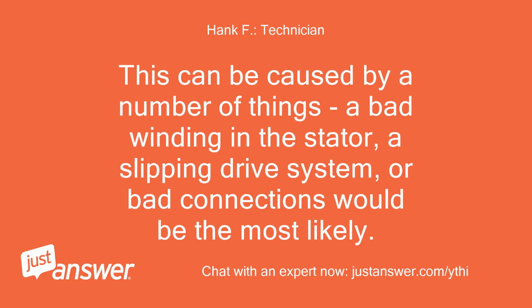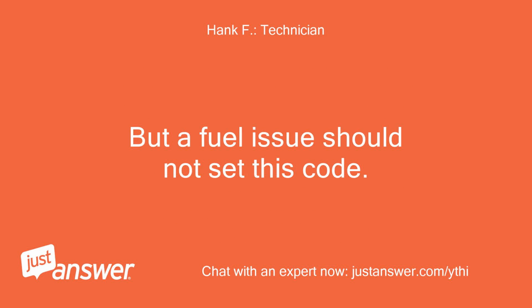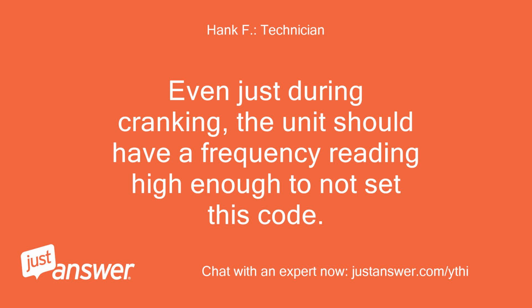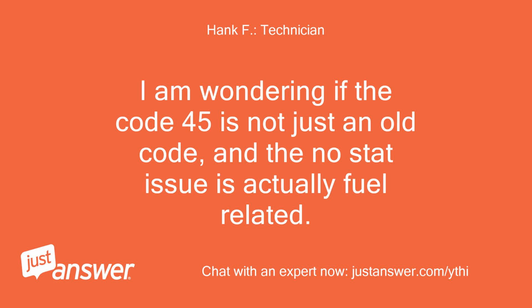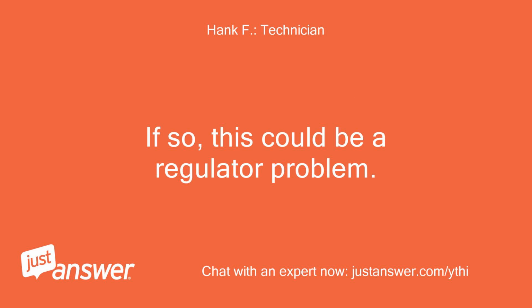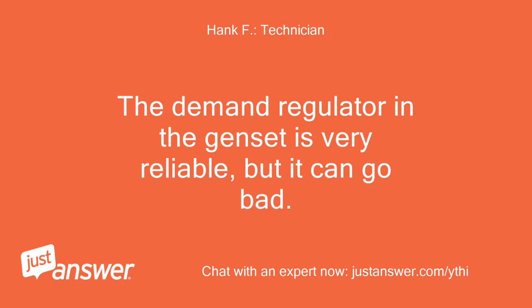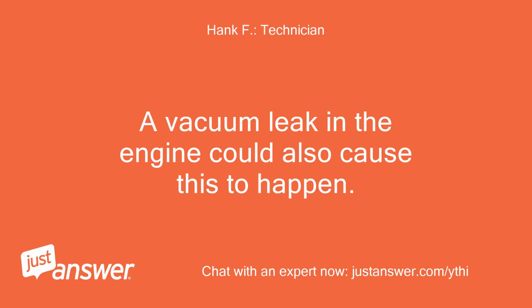This can be caused by a number of things. A bad winding in the stator, a slipping drive system, or bad connections would be the most likely. But a fuel issue should not set this code. Even just during cranking, the unit should have a frequency reading high enough to not set this code. I am wondering if the code 45 is not just an old code, and the no-start issue is actually fuel-related. If so, this could be a regulator problem. The demand regulator in the genset is very reliable, but it can go bad. A vacuum leak in the engine could also cause this to happen.